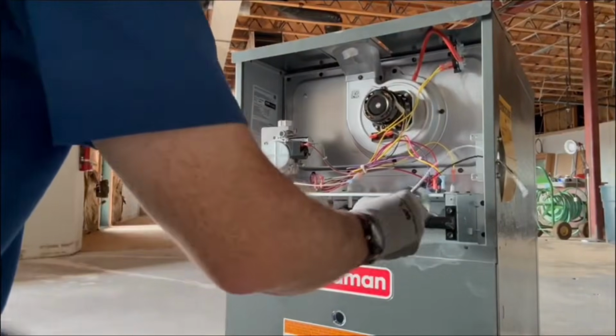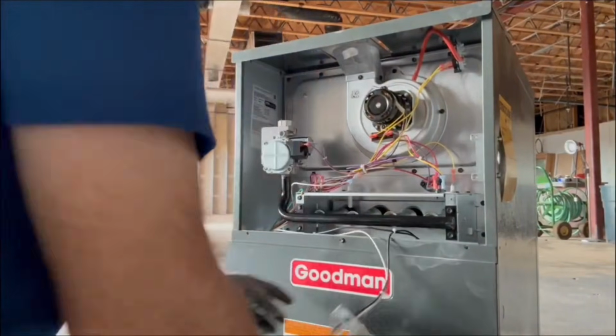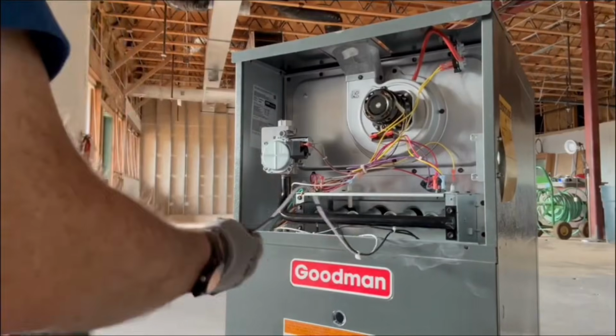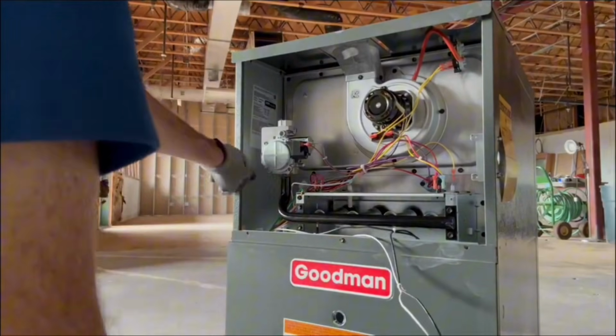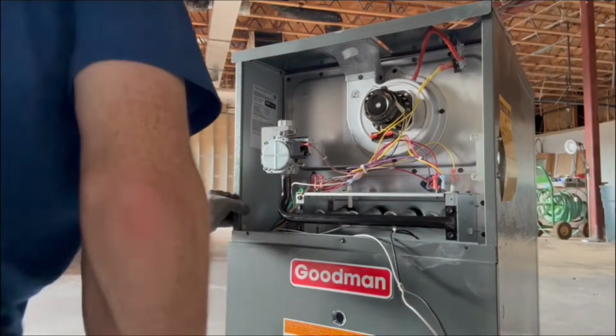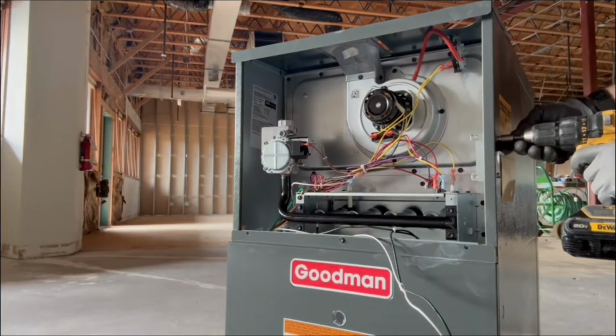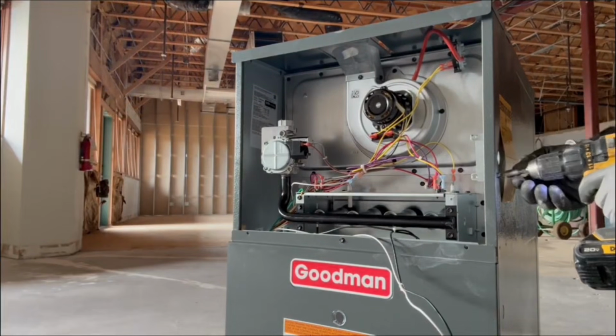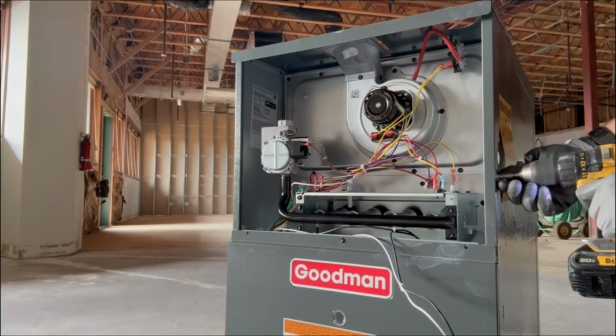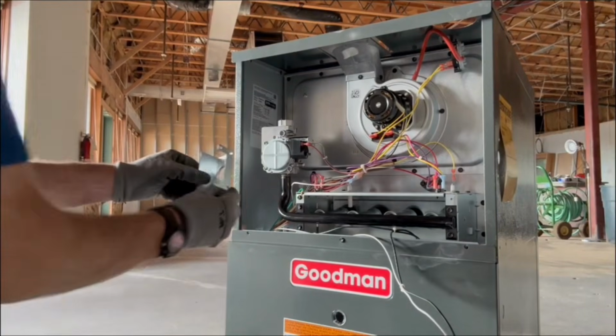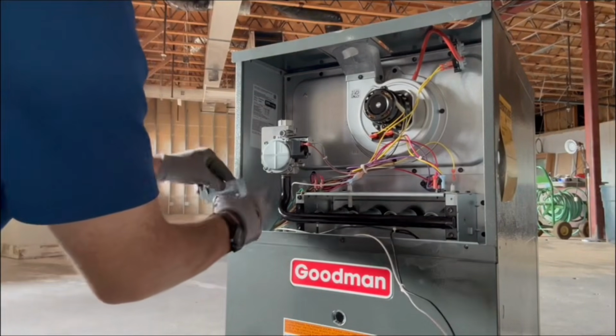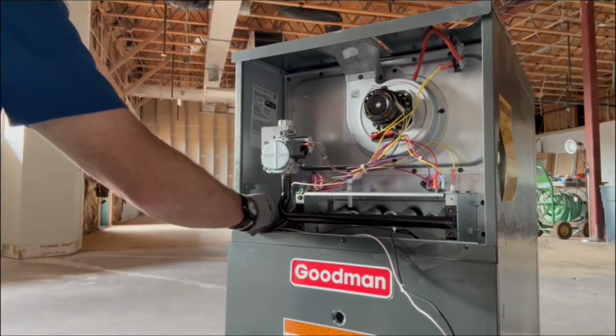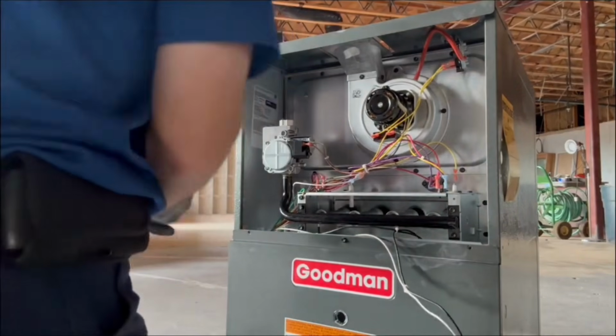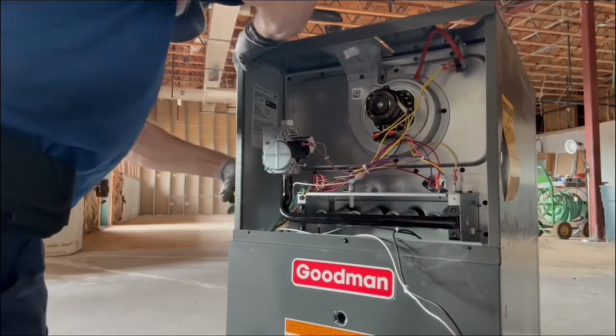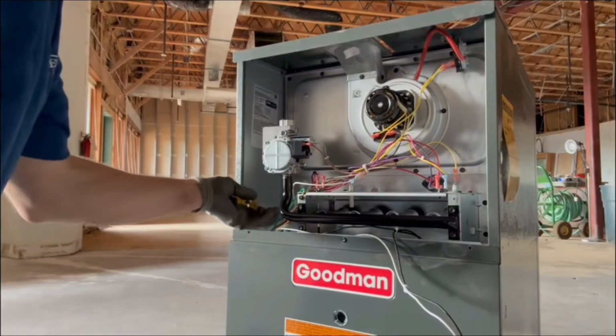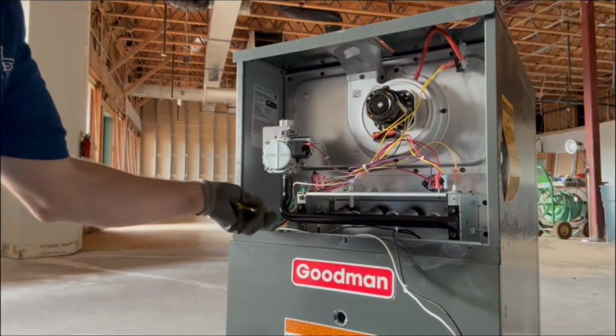And so this one had the wires coming out the right side. That's not going to work for our application. We need it coming in on the left side, right here. So I'm going to drill my holes. I'm going to reuse the mounting hardware, and then I'll have to patch or cover those existing holes, again, because it's an A2L slightly flammable refrigerant. You don't want to have holes in the cabinet. If A2L refrigerant were to leak out, you don't want it getting inside the combustion chamber.